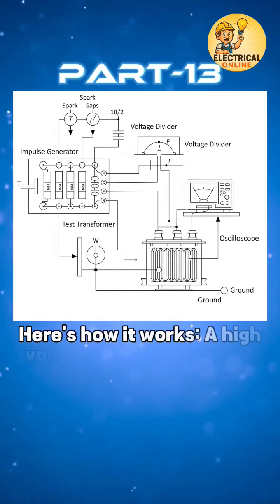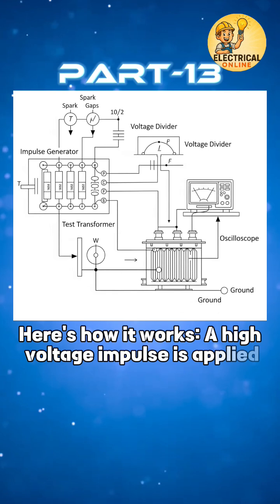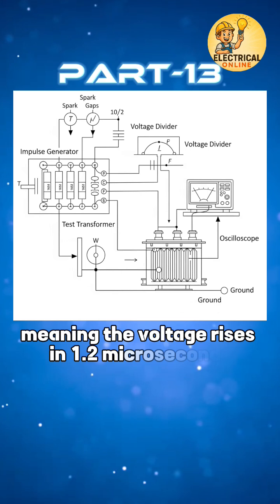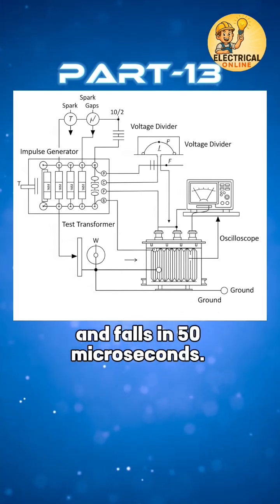Here's how it works. A high voltage impulse is applied, often 1.2/50 microseconds, meaning the voltage rises in 1.2 microseconds and falls in 50 microseconds.